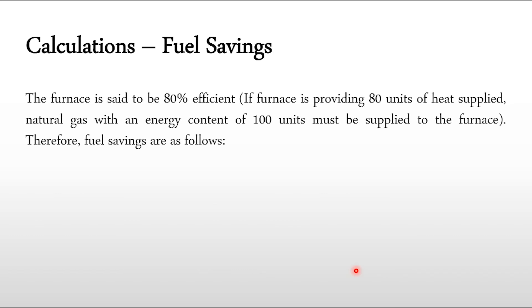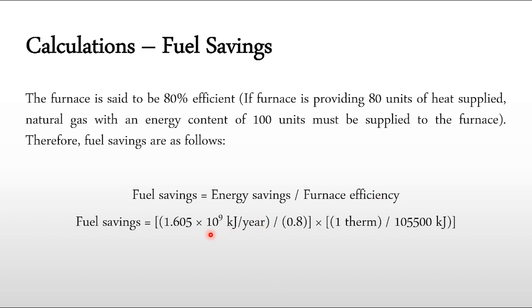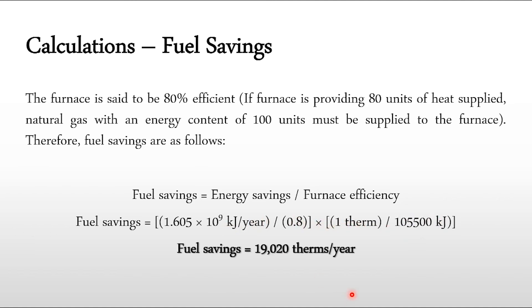From the energy savings we compute the fuel savings. The furnace has 80% efficiency, meaning 100 units of fuel input yields 80 units of heat. Fuel savings = energy savings / furnace efficiency = (1.605 × 10⁹ kJ/yr) / 0.8, then divided by 105,500 kJ/therm to convert to therms. The result is 19,020 therms per year saved.